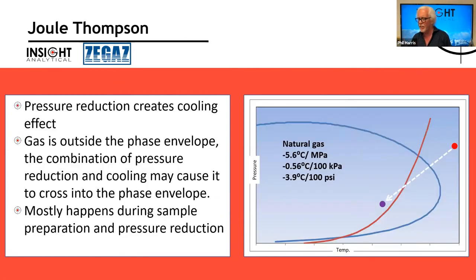And then there's this Joule-Thompson effect. When we go across a regulator, whether it's a process regulator or a sample system regulator, and we drop pressure, natural gas drops by about 0.56 degrees C for every 100 kPa. So that's about 3.9 degrees C. If you want to work in PSI, it's around 4 degrees C for 100 PSI, around 6 degrees C for a megapascal. But every time we drop the pressure, the temperature drops as well. So when we go across a process regulator or a sample system regulator or a needle valve, we run the risk of hitting a dew point right there.